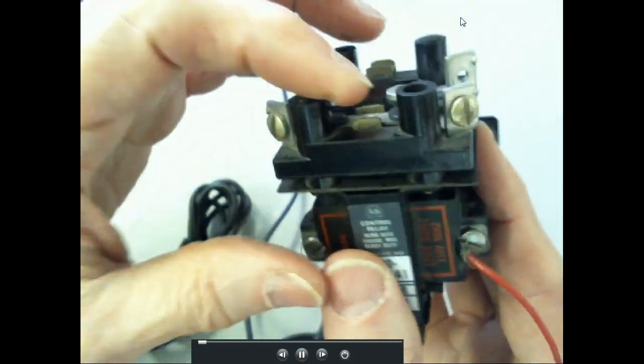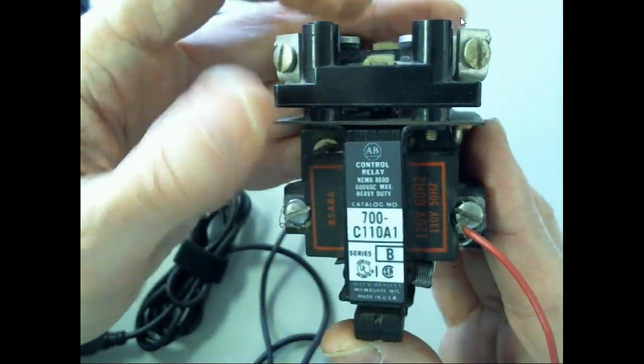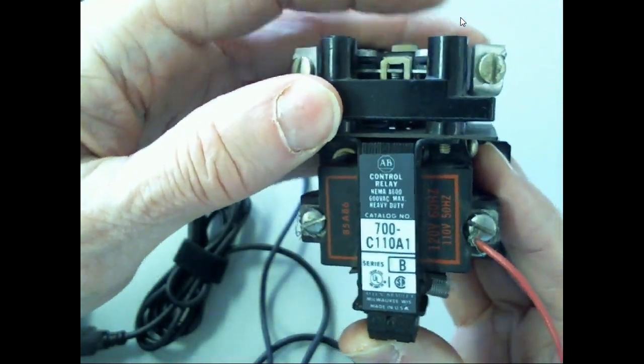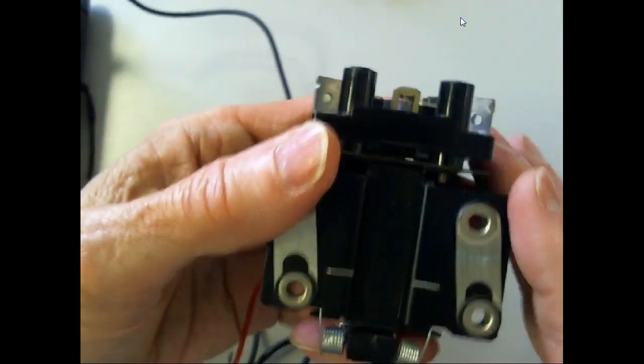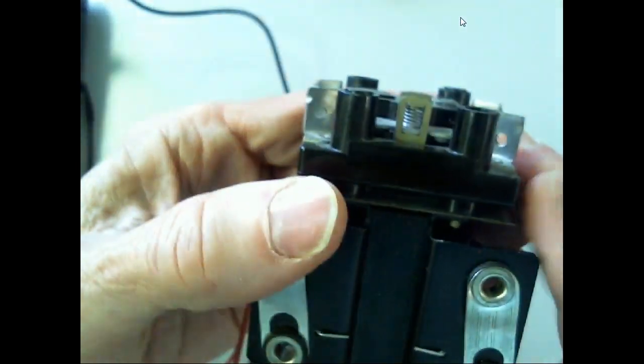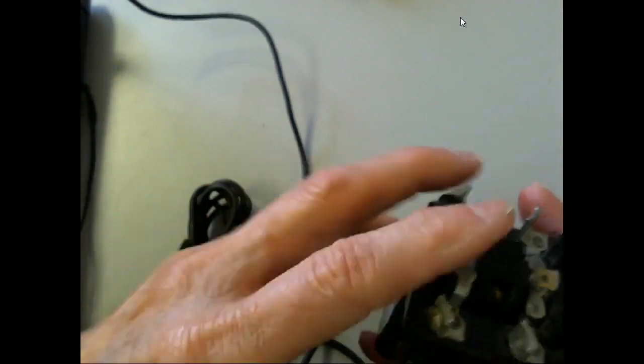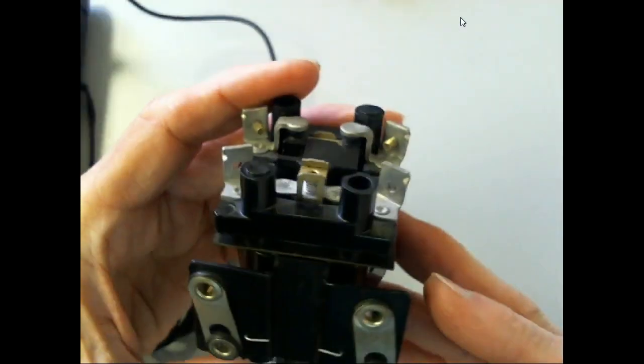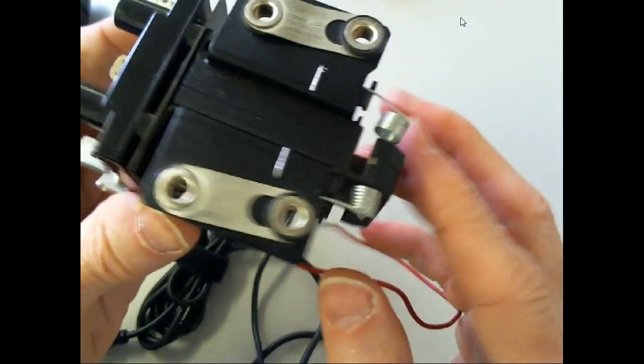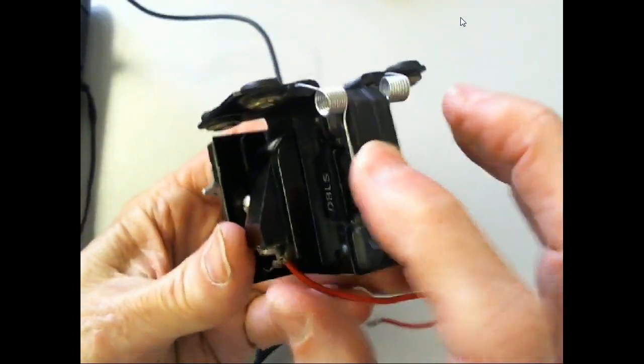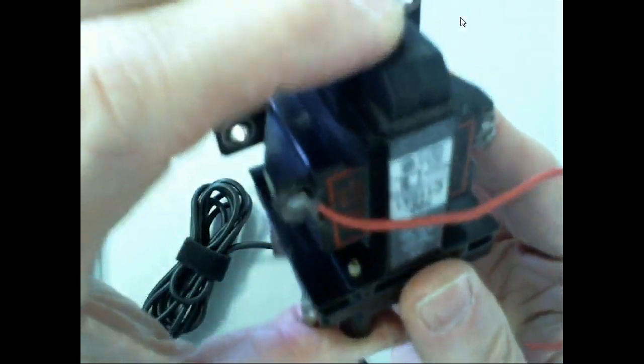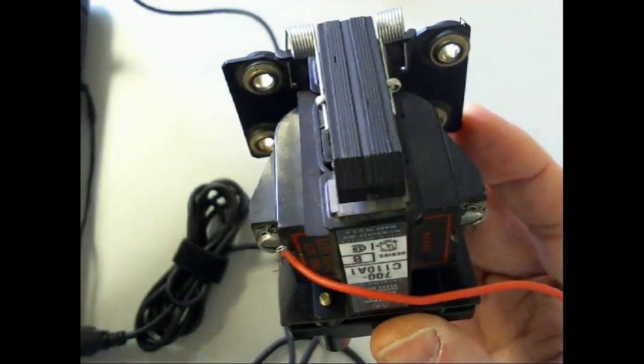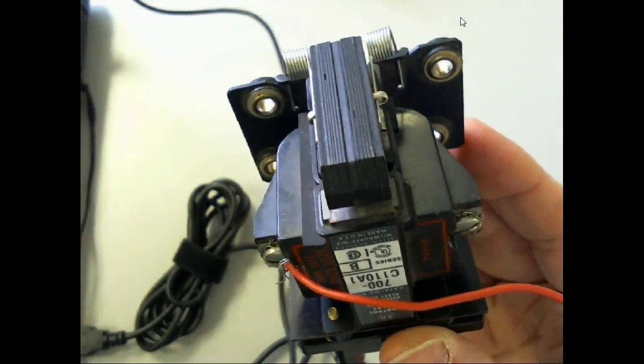Now notice what it's doing. This set of contacts is going to close. This set of contacts on the bottom, on the other side, is going to open. So this has one set of contacts. And then this has these springs down here. So no matter how I mount this, it's going to work the solenoid.